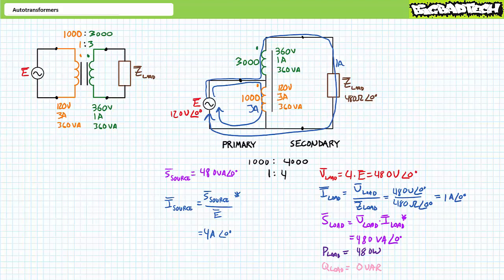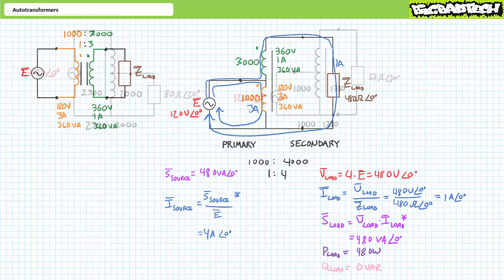Again, consider the amount of power capable of being transferred by the autotransformer. Recall that when configured as a traditional transformer, it was limited to a rating of 360 volt amperes. These same windings configured as a step-up autotransformer allow the device to transfer 480 volt amperes, an increase of 1.33 times, again without exceeding the rating of either winding.